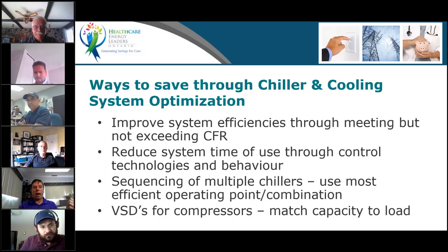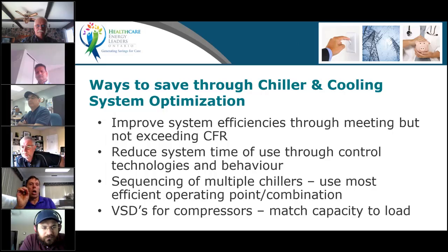And the type of chiller. Is it inlet guide vanes, or is it VFDs or VSDs? The VFD chillers are actually more efficient at part load, so you will sequence them differently than if you have inlet guide vane chillers, or if you have a magnetic bearing chiller. They're way better at part load, so you would tend to run them more often in parallel than in sequence, in lead lag, for example. So those are all things that when you have a central chilled water plant, you need to know properly.